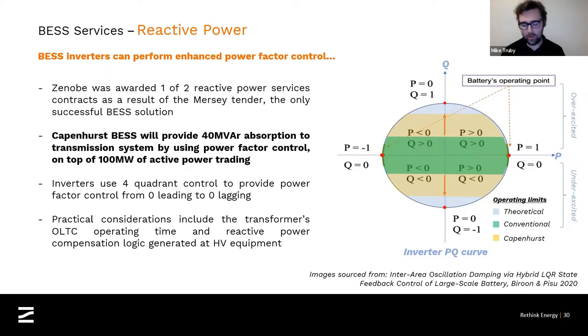The way an inverter works is that we have what you call quadrant control. Depending on what the inverter is designed to do, it can operate in 1, 2, or 4 quadrants. The quadrants describe how much real and reactive power the inverter is capable of injecting or absorbing from the system. Theoretically, an inverter with 4 quadrant control, which is what the inverters at Capenhurst are, is capable of injecting 100% of the battery energy as real power, or absorbing 100% of real power, or doing it as reactive power. But in practice, there are limitations to what inverters can achieve.